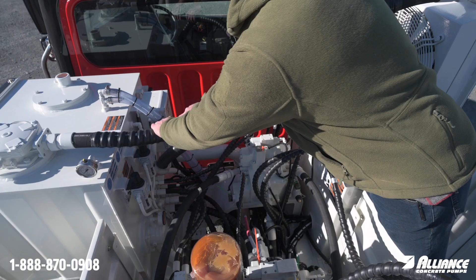The thing that I'm leaning on here is what we call your tank pressure relief valve. So if potentially the system gets warm, expansion and contraction, these valves will open to drain off excess pressure. So there's 2 pressure relief valves right here, and there's a third one down here. This one's set at 1 bar down here, and then it's set at 1.3 bar, 1.7 bar. So those, they're all adjustable and can be serviced if there's an issue.